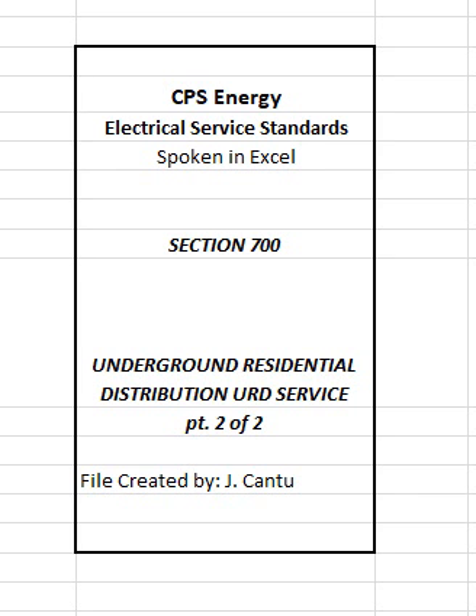704 Not permitted under buildings or structures. Underground service lateral conduits shall not be installed under buildings or structures. Customer shall install metering equipment and provide service disconnecting means and overcurrent protection before service entrance conductors enter into buildings or structures, refer to Section 400.